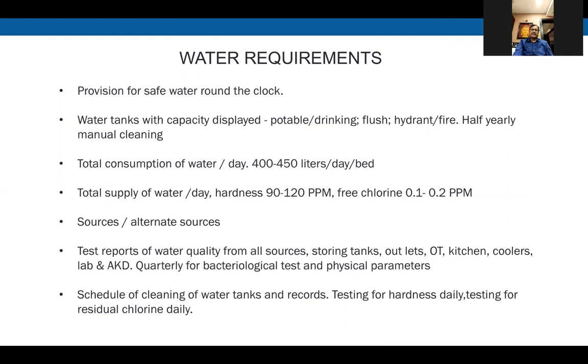If the free chlorine is more, then it is also problematic, because all your filters, etc. will get clogged. They will deteriorate very fast because chlorine itself will kill these filters. Various alternative sources nowadays, it has almost become compulsory in metro cities and various other cities also, where we are getting tanker water. So we must get this tanker water tested quite often.